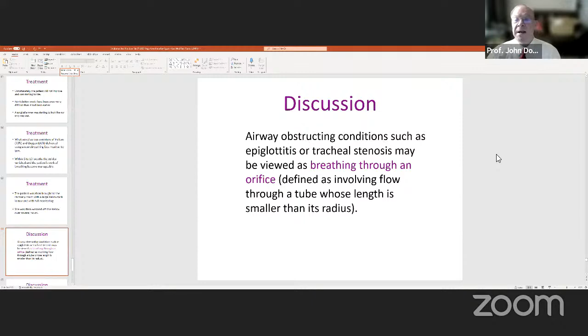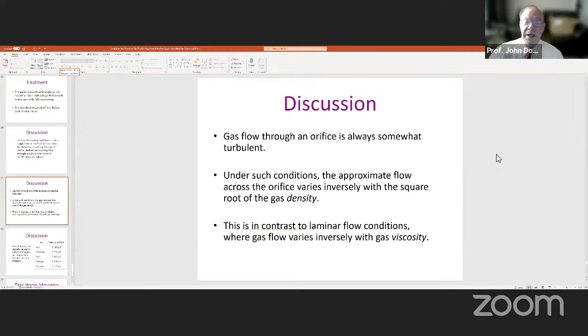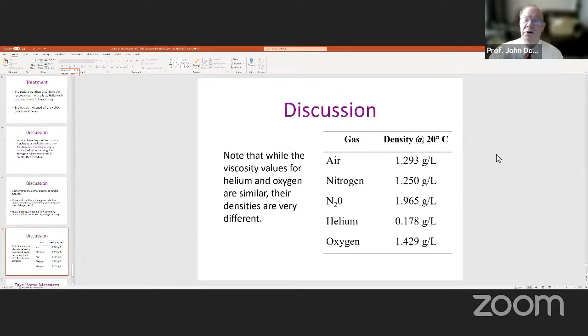Gas flow through an orifice is always somewhat turbulent, and under such conditions, the approximate flow across the orifice varies inversely with the square root of gas density. This is in contrast to laminar flow conditions where gas flow varies inversely with gas viscosity. And here we can see, comparing oxygen, helium, nitrous oxide, and other gases, the various densities. You can see the helium at a density of 0.178 grams per liter is much more favorable than oxygen at 1.4 grams per liter in order to reduce turbulent gas flow.